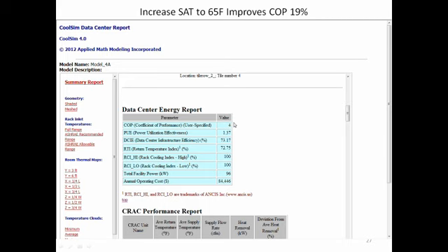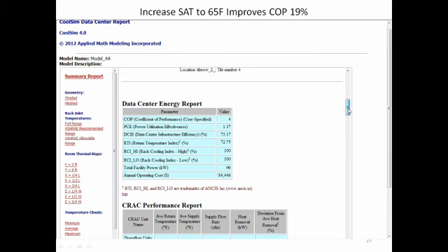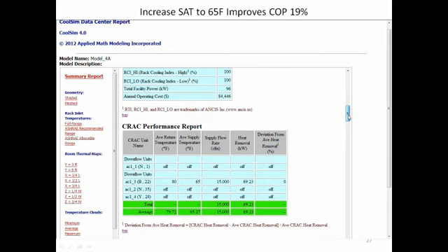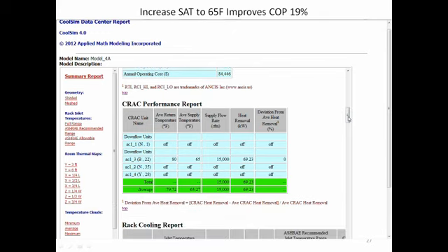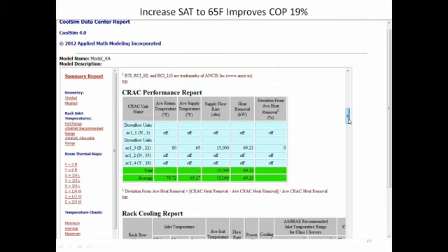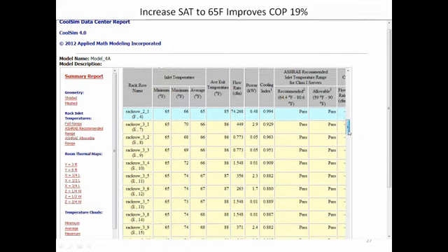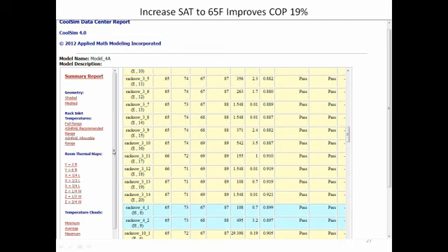But there again, yeah, it's a good idea to do the simulation with one, if you know that's the way you're going to run, to do the simulation with each one of them on, individually. That's exactly all alone, just to make sure that the flow patterns can handle it. Yes. Flow in the room is adequate for it. Exactly correct. So what you would want to do here, right now I've got this particular CRAC unit turned on, AC1_3. I'd want to switch them, rotate them around, try this same model with each of the others turned on individually to make sure that it conforms to the specification. If so, you could set the icon unit up so that any one of the other three would come on, and you'd still have your N+1 case. So this one works pretty well.